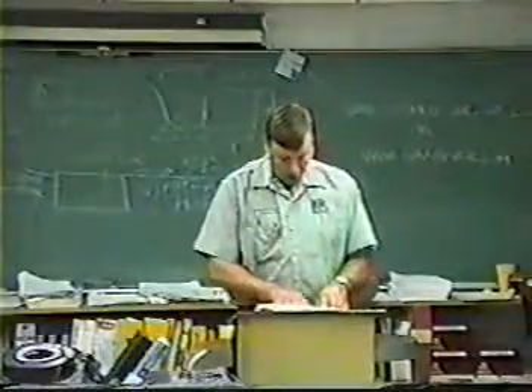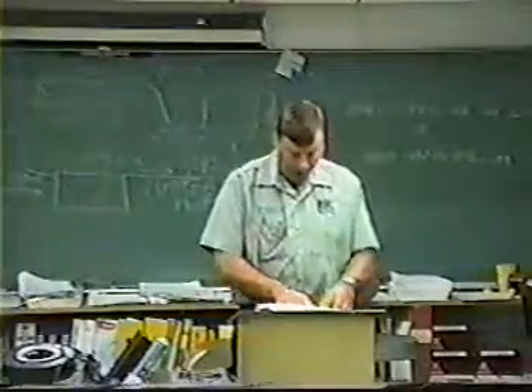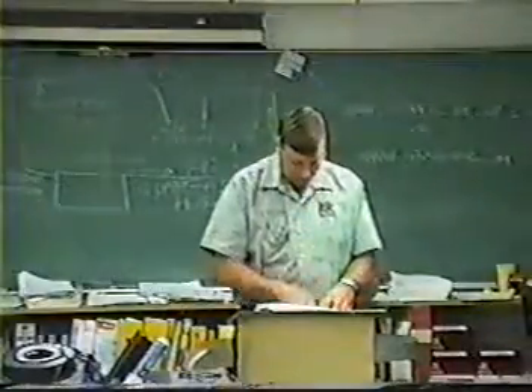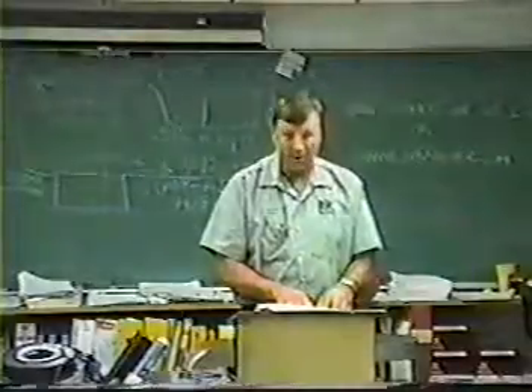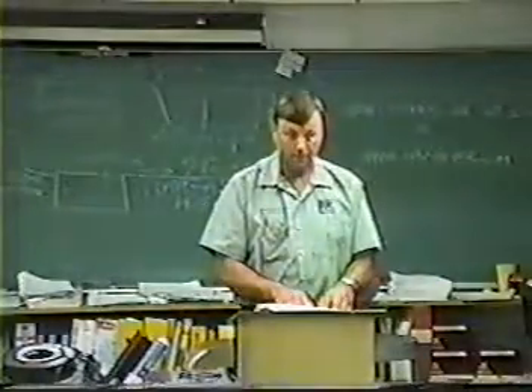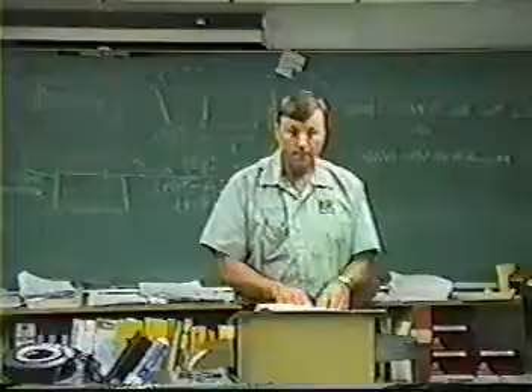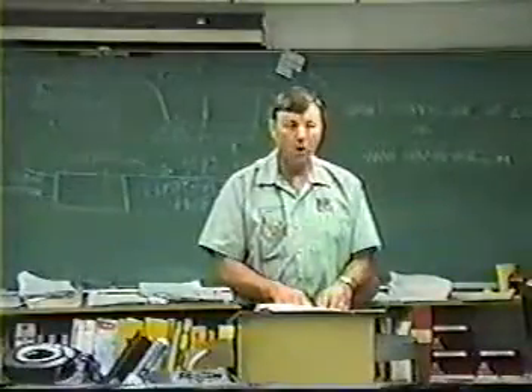Okay, R11 at 4 degrees. If you look at R11, the very first one in the orange tank, 15.6 vacuum. That parenthesis means vacuum. That'd be the suction pressure of a chiller using R11, on low pressure.